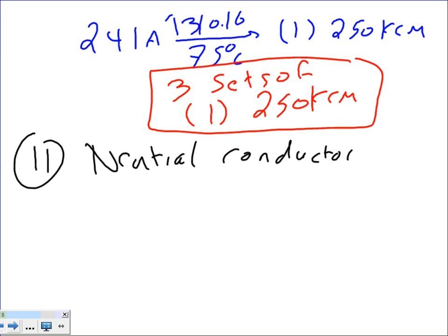For the neutral conductor, guys, here's what I want to remind you: the neutral conductor on the secondary side is only going to see the neutral current. So what was the neutral current, or the single phase current? The single phase current was 208 amps.